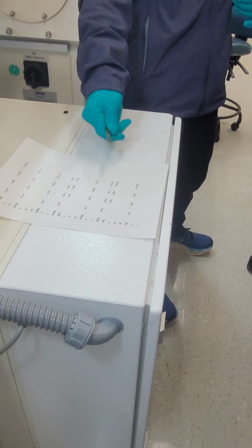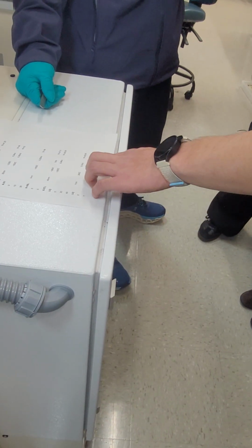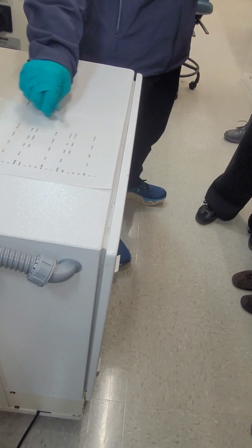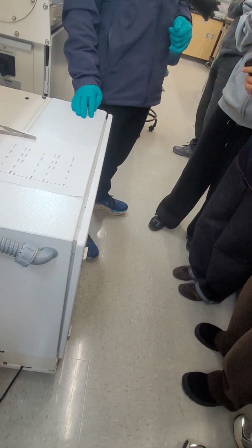We grow a layer, and we see it's slightly off. So we want to grow 10 nanometer, but then we grow, say, 11 nanometer, and then we tune down this factor to make it 10 nanometer, things like that. This is the tooling factor. Yeah, actually, it can be very precisely determined. Otherwise, we couldn't do 5 nanometer material. So we have to have very precise control of the growth rate.